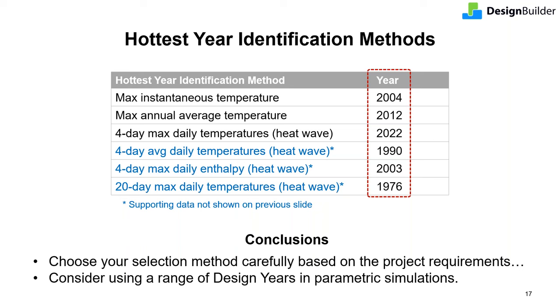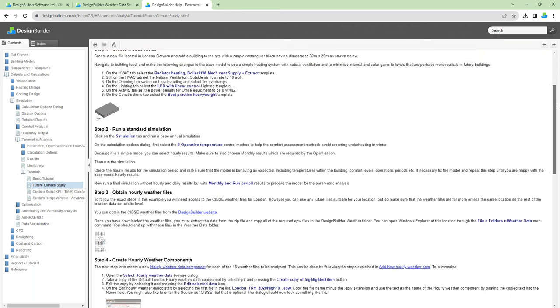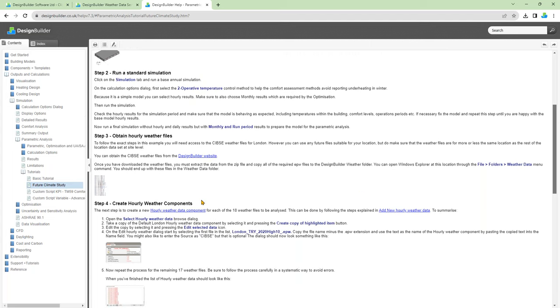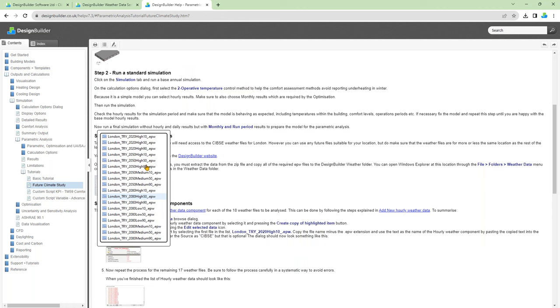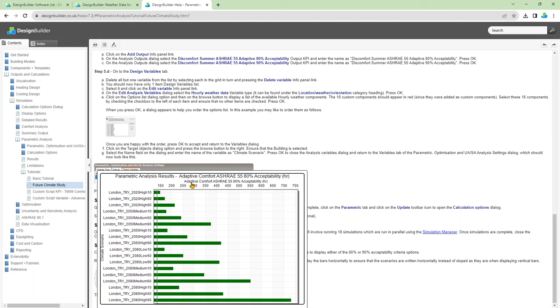It won't always be clear which selection method to use, and in this case you can download weather data for a range of worst case years and check designs using all of them. In our example, you could download all the design years in the table and use parametric analysis to see how a building performs across the range of worst case weather scenarios. The Design Builder program help includes a worked example showing how to check building performance across multiple weather files using parametric analysis, with step-by-step instructions explaining how to set up a parametric overheating study based on adaptive discomfort using weather data as the variable, and how to plot the results for all weather files together in histogram form.